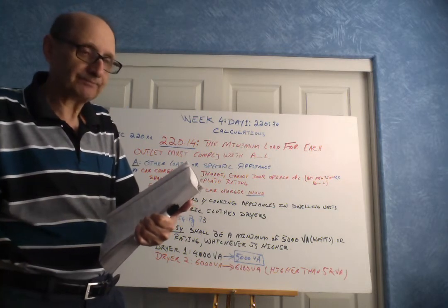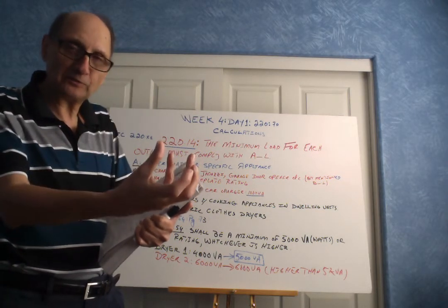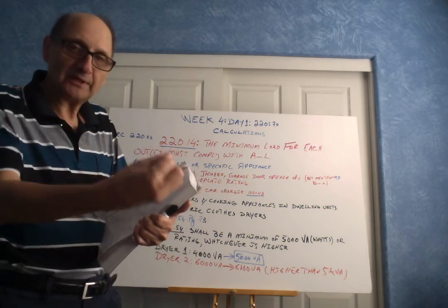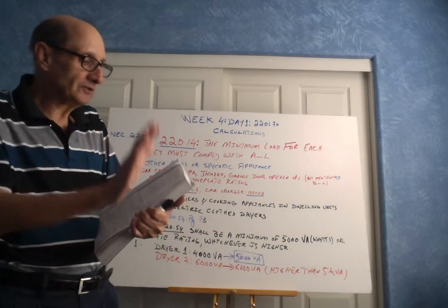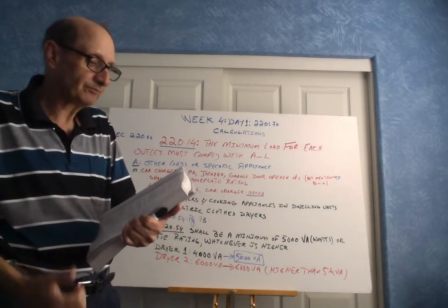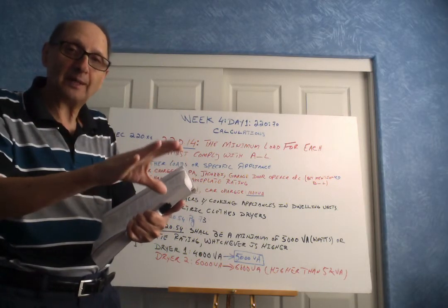That means whatever value you see, you get. You don't need to multiply it by anything. But once you go past 4, so if you have 5 electric dryers, then the demand factor drops to 85%.